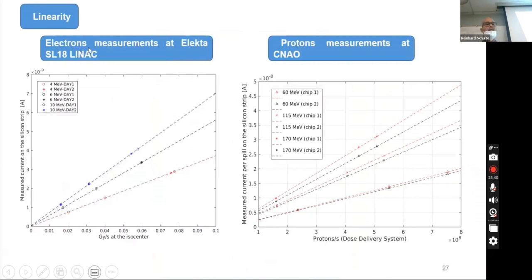Here are the results in electron measurement at the Elekta SL18 Linac that we have in our university. We can see here the measured current on the silicon strip versus the gray per second at the isocenter. You see three different energies, 4, 6, and 10 MeV, for 2 different days. We see a very nice linearity of our data. This confirms good linearity because we made a linear fit with 0.99 R squared.